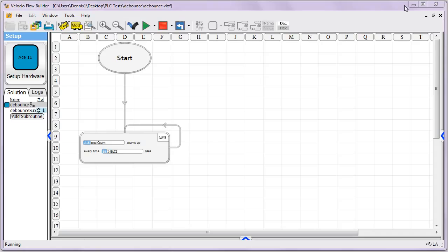transition. It's very, very quickly done, but our PLCs in a typical application will run around 5,000 scans per second. So they run fast enough that they will frequently catch these very rapid transitions. So you want to sometimes slow down the process a little bit for particular inputs. You wouldn't want to do this for all your bits, but just your input bits may sometimes require this to kind of filter out those mechanical bounces.